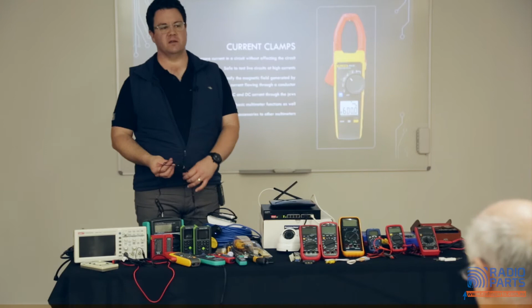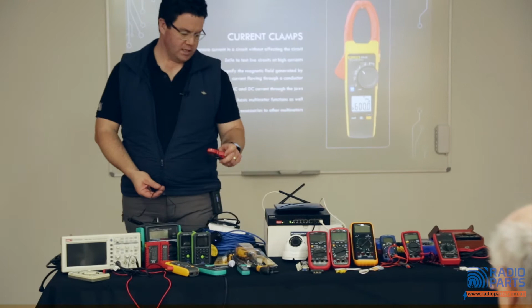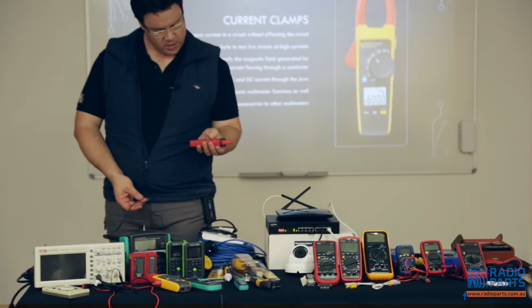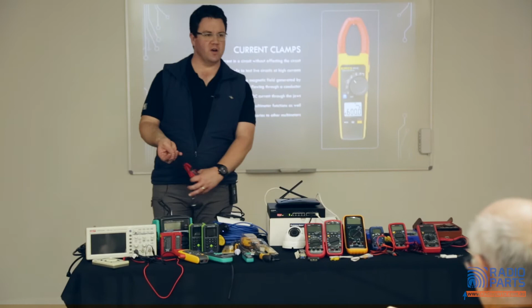Depending on the clamp you've got, you may also be able to measure DC current, though it's a different type of clamp. So with this one, if I go to the amperage range and put it into a little DC circuit, through here - measuring 0. Take the other cable - still measuring 0. But there is DC flowing through this, because my little camera behind here is actually working. This clamp doesn't have the right type of jaws, so it can't measure DC current that way.